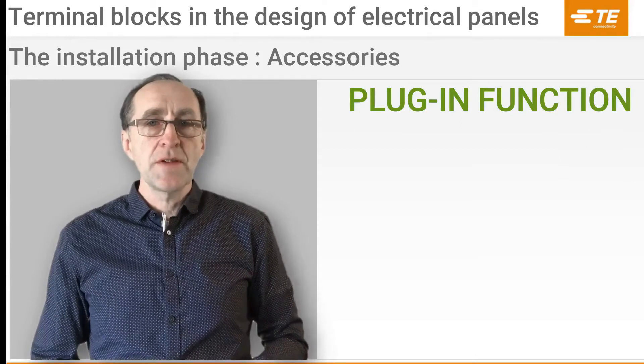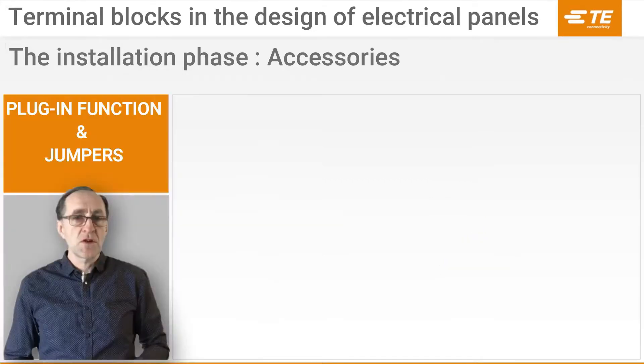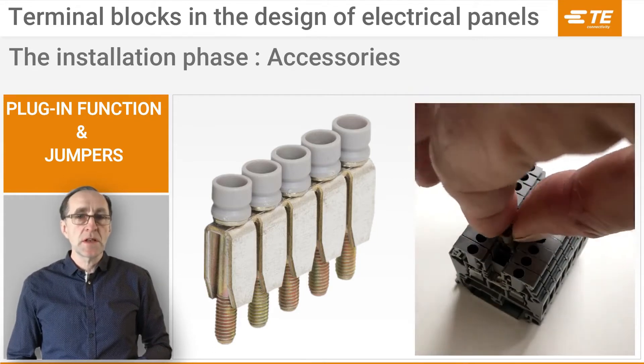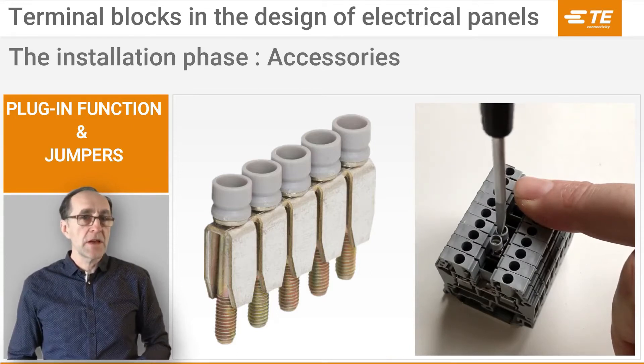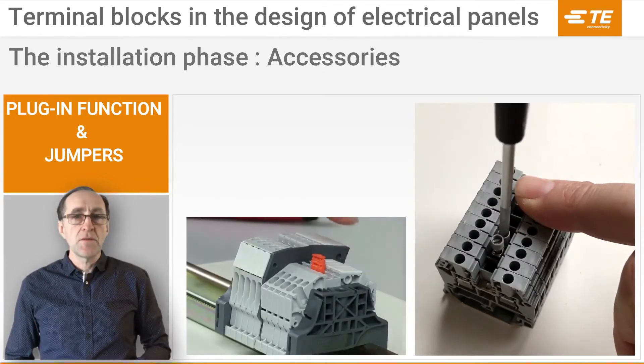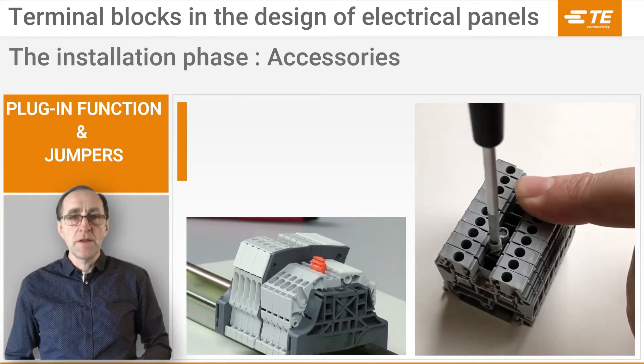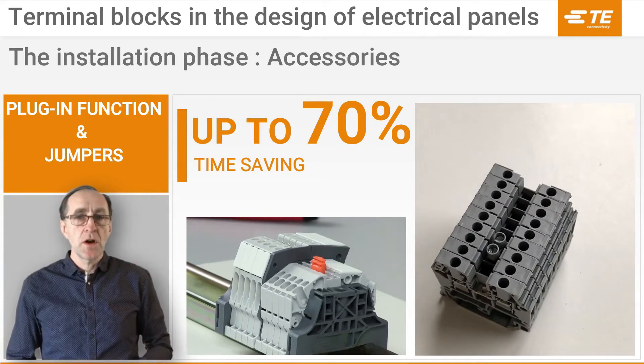First, the plugging function. Many of our accessories are designed to be plugged into the terminal blocks. Let's see this on a jumpering system. Traditional jumpering solutions use screw-type jumpers which are installed in the center of the block, with each pole then being individually tightened. As you can see here, the SNK series jumper can be plugged into the terminal block by hand in one single operation. This saves up to 70% installation time for a two-pole jumper, even more when using a higher number of poles, compared to the traditional screw-type jumper on the right.